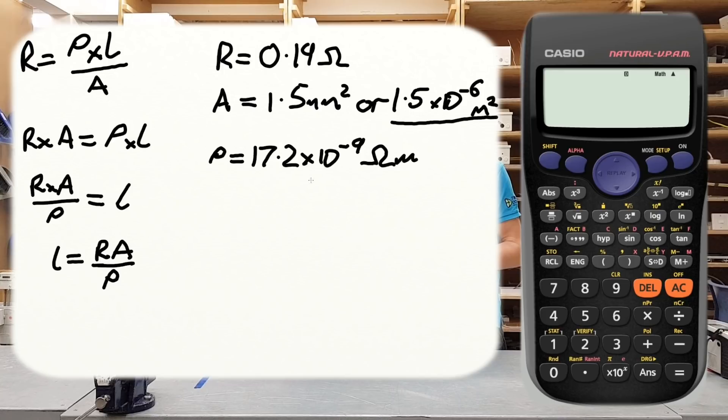So now we've got all of our numbers in place, so we're going to use this number, this number, and this number. We'll put those into the calculation and see what we end up with. So we'll start that again. We're going to say that the length of the conductor will be equal to the resistance 0.19 times by the cross-sectional area, which is 1.5 × 10^-6, and then we're going to divide that whole thing by 17.2 × 10^-9. So that's what we're looking at there. So we can now put this into our calculator and figure out what the length of the cable should have been. So we'll head over to our Casio FX-85 GT Plus, beautiful calculator as it is, and we'll put that in.